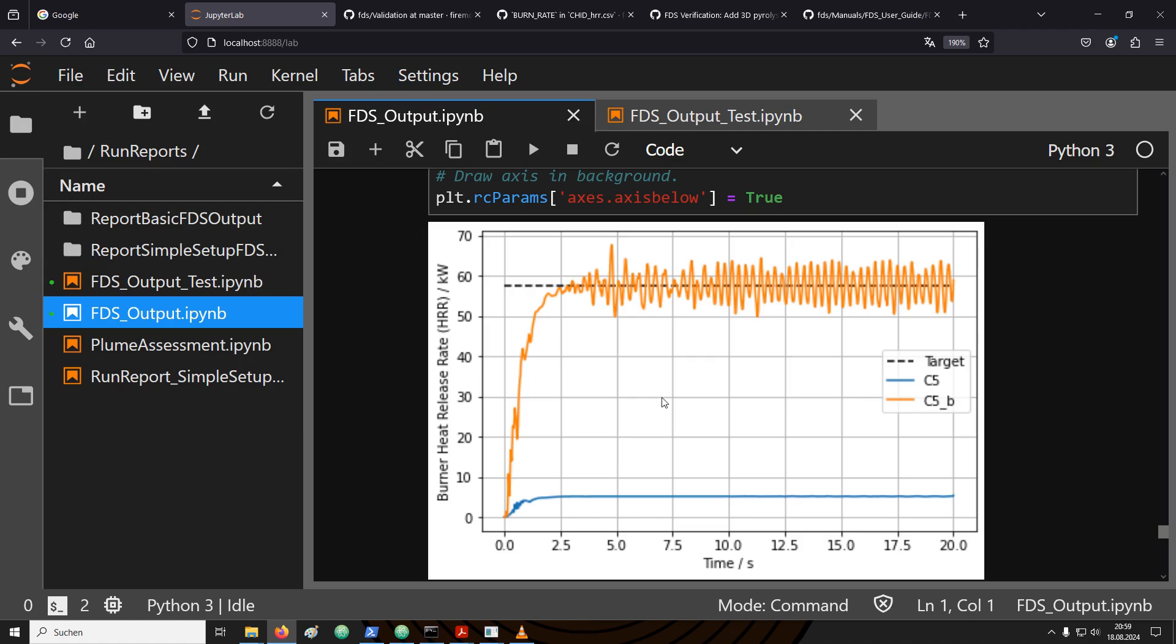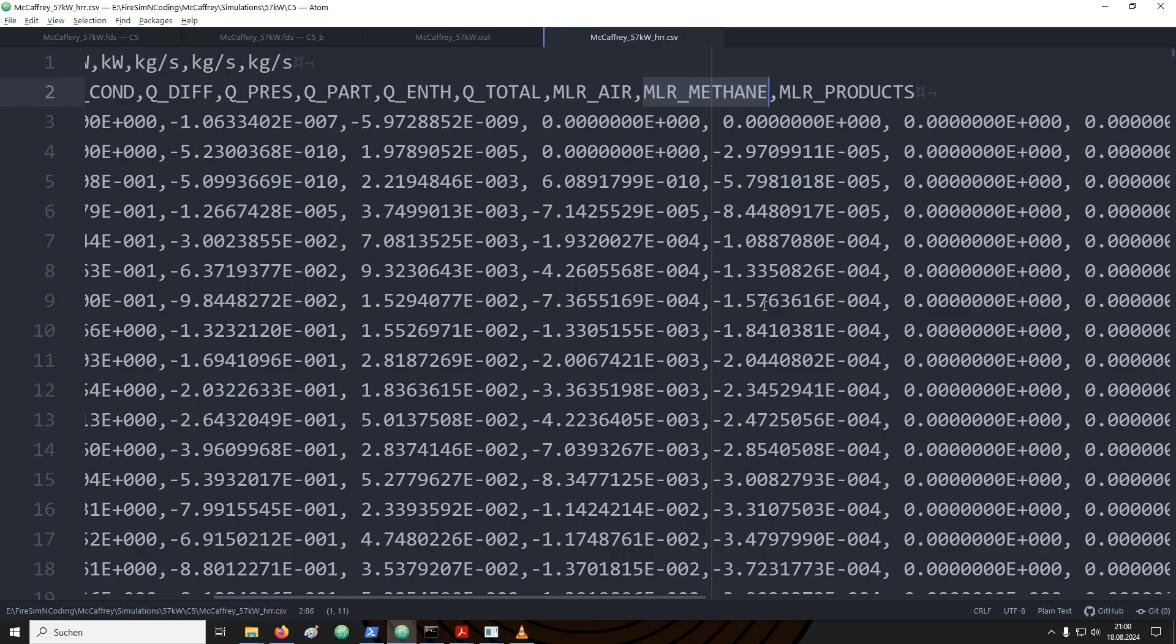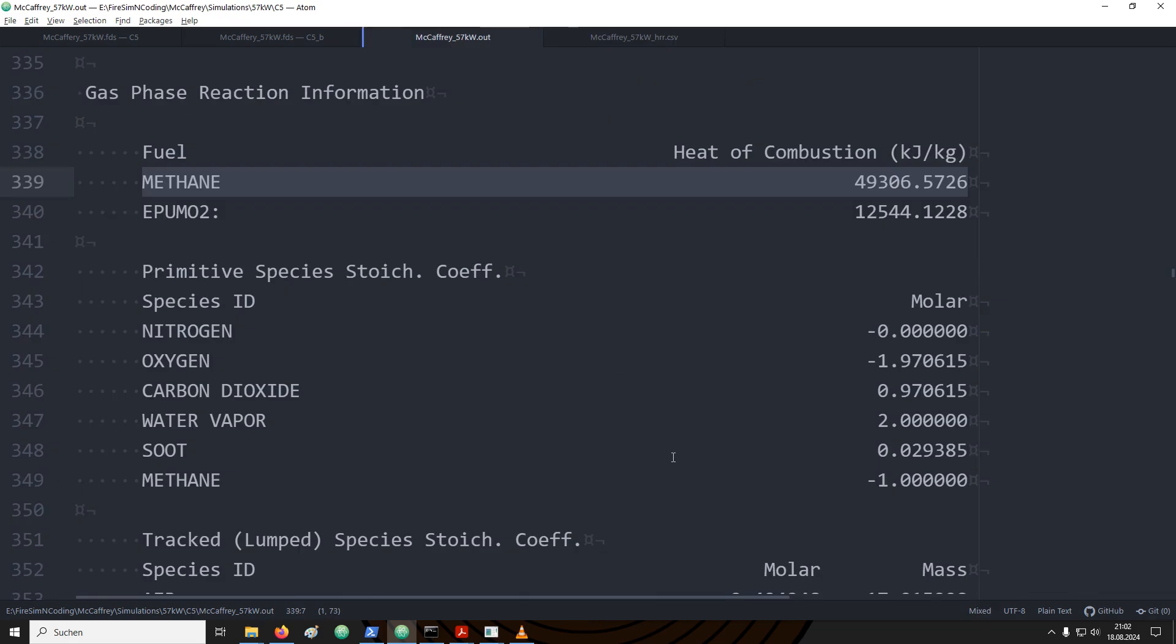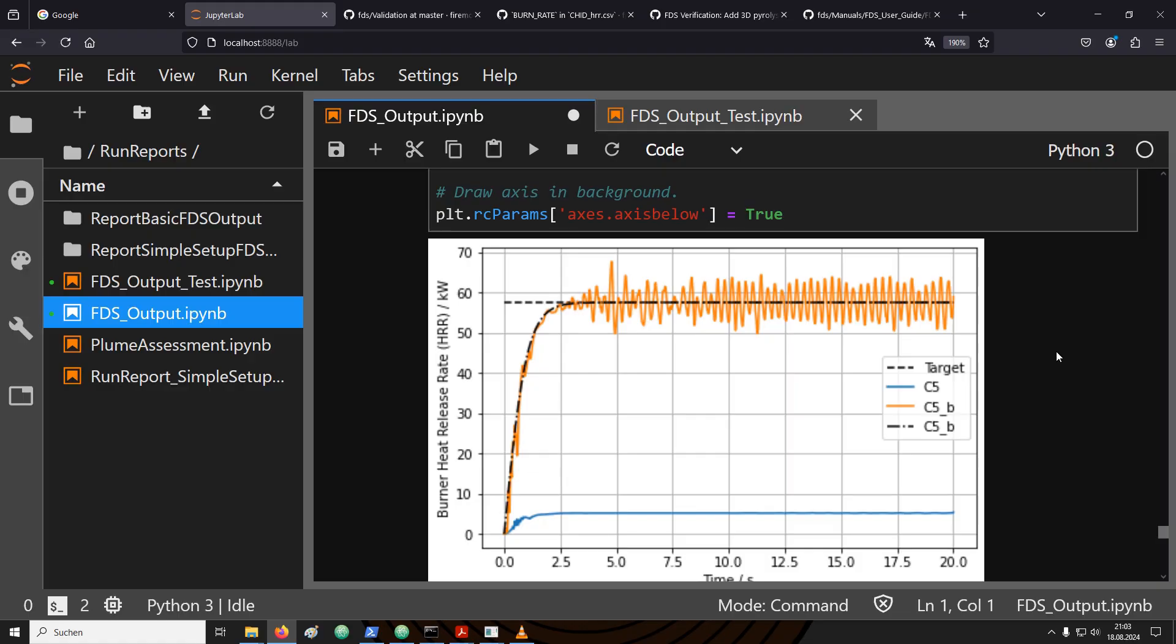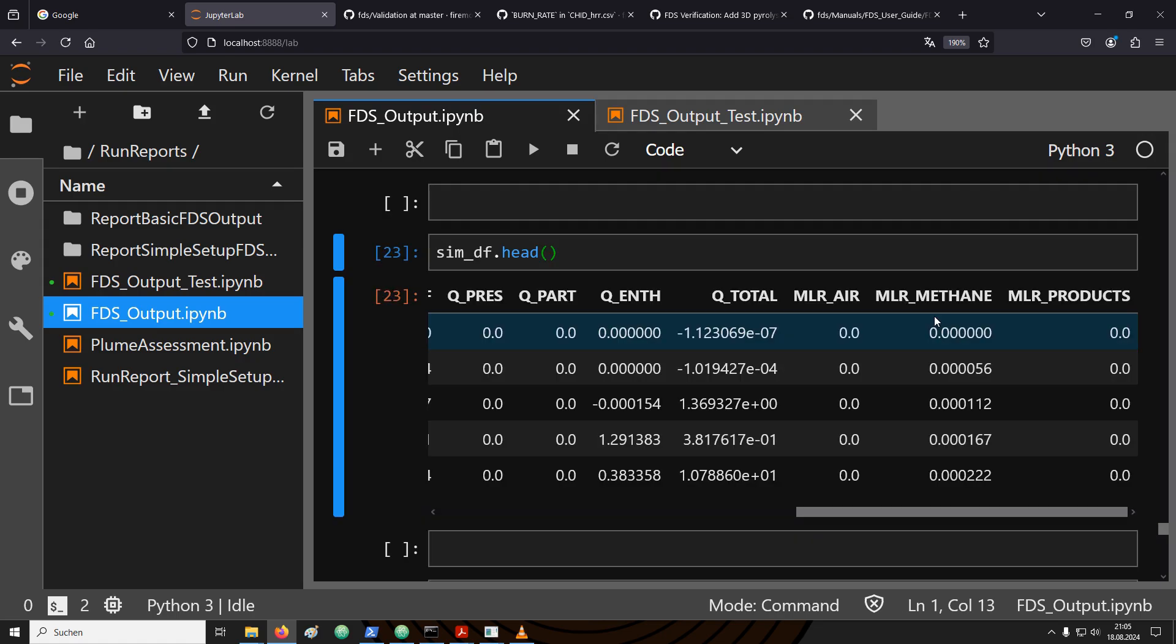We have been talking now all the time about the heat release rate. But I said before that the HRRPUA produces the mass flux. So how exactly is FDS coming to this value? We can have another look in the HRR file and see that there is also a couple of mass loss rates being presented. The mass loss rate of air, the mass loss rate for methane and the mass loss rate for the products. These are the gaseous species that we have already seen in the out file. Also remember that in the out file, a value for the heat of combustion for the combustible gas is presented. We can use this value for the heat of combustion with the mass loss rate for methane to compute what the heat release rate should look like. This is demonstrated in this plot here with the black dash dotted line. FDS, however, does the same computation backwards. You provide a value for the heat release rate. FDS knows what the heat of combustion is and from this calculates backwards what the mass loss rate needs to be.